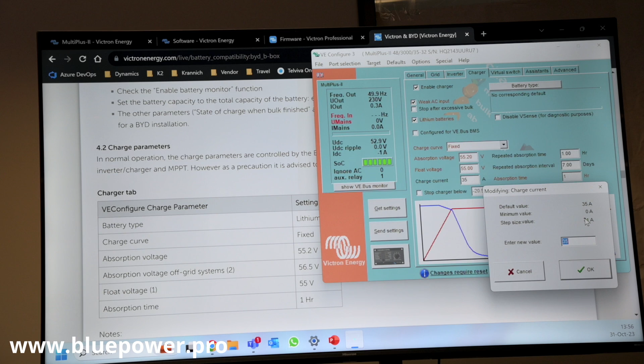If you've got multiple inverters, take note not to overcharge your battery, because with 3 inverters, that charging current is going to be multiplied by 3. So if our battery can only handle 100 amps, I'll have to divide 100 by 3 and input that, which is 33.